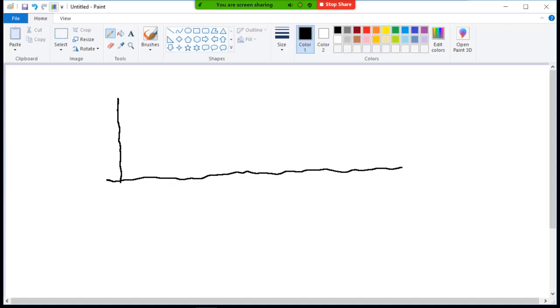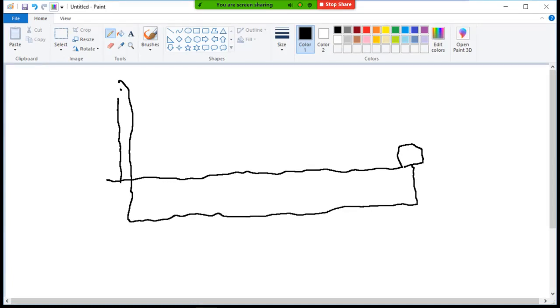Another big one we saw out there with some engineers: I've got wire that comes down a pole, and here's ground level. My ground's lumpy, and I'm going to a transformer that sits on the ground. So you got to come from the top of the pole, down 4 feet, over here, up 4 feet, and even with a wheel, they will wheel off from here to here, and they will tell you how much you need. 100 feet.